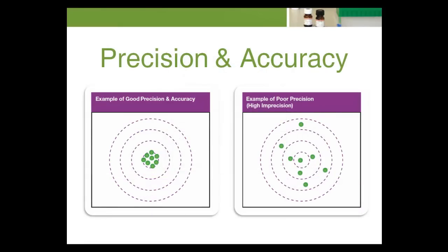Standard deviation is calculated for control products from the same data used to calculate the mean, and provides the laboratory an estimate of test consistency at specific concentrations. The repeatability of a test may be consistent — low standard deviation, low imprecision — or inconsistent — high standard deviation, high imprecision. Inconsistent repeatability may be due to the chemistry involved or to a malfunction. If it's a malfunction, the laboratory must correct the problem.